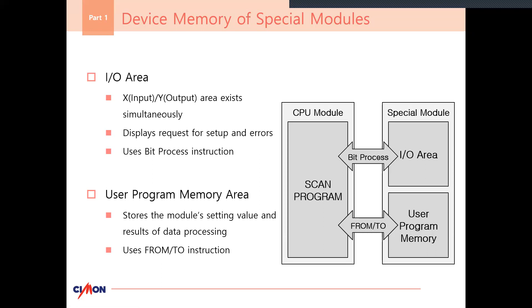So when you look at the IO area, you have X for input, Y for output, and they're used simultaneously. Every special module is essentially allocated 1 word of X data and 1 word of Y data. That is 16 bits for X and 16 bits for Y. And that is just by default. There are exceptions, and we will cover those exceptions. The user memory area is also referred to as buffer memory area. This is where the data is stored inside the module, and it's retrieved using FROM or TO.